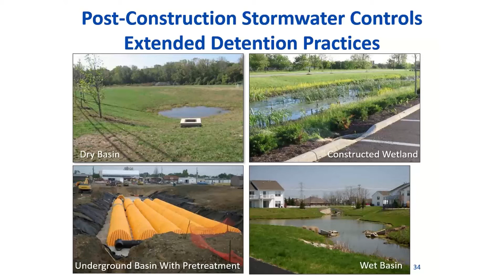As I mentioned, extended detention works by draining the water quality volume over an extended period of time, and each practice has a specific minimum drain time optimized for its treatment performance. So wetland and underground basins cannot drain the water quality volume in less than 24 hours, and dry basins can't in under 48 hours. And the way to measure this is by using equations or software that calculate the drawdown by pulling an imaginary plug from a full basin and measuring the outflow, which is referred to technically as a static drawdown with zero inflow.